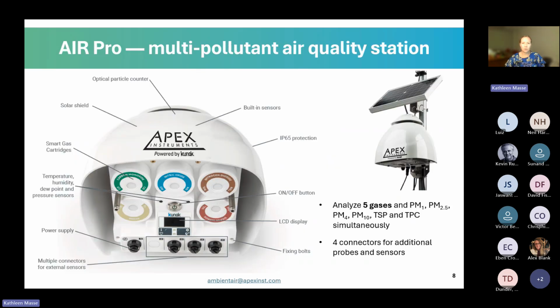This slide shows a closer look at our Air Pro system. At the bottom is where the gas cartridges connect — you can connect up to 5 different gas sensors — and the top of the unit is where the PM sensor is positioned. There are built-in temperature, humidity, dew point, and pressure sensors, which help maintain the quality control of the data generated by the sensors. There are also additional connectors in the lower part of the base station for connecting the meteorological sensors.